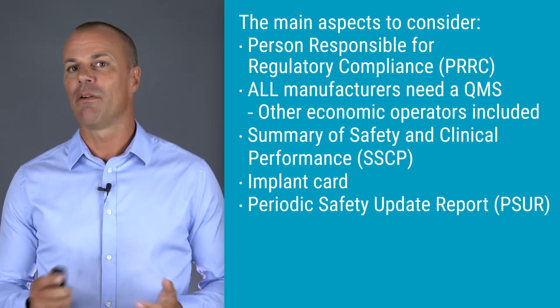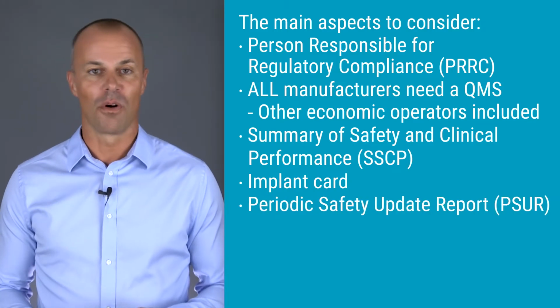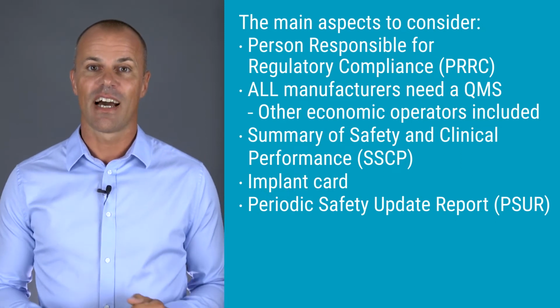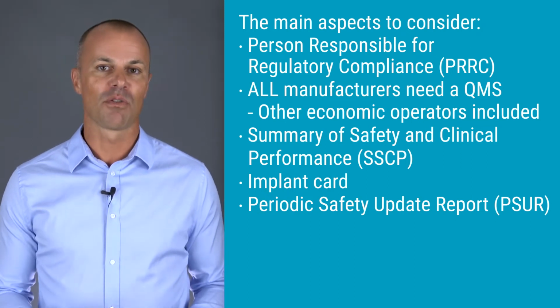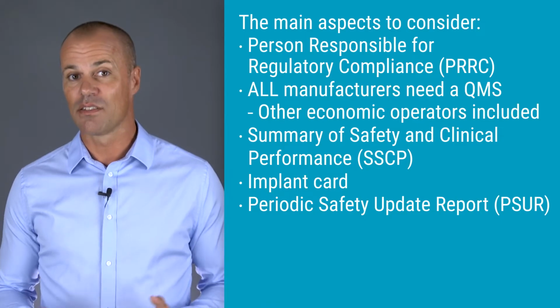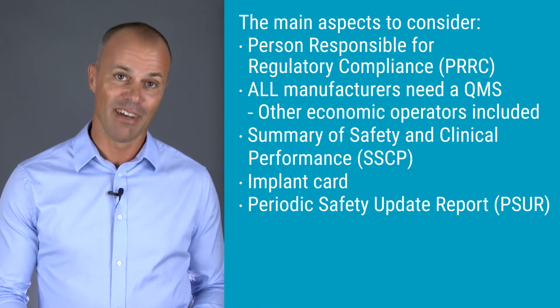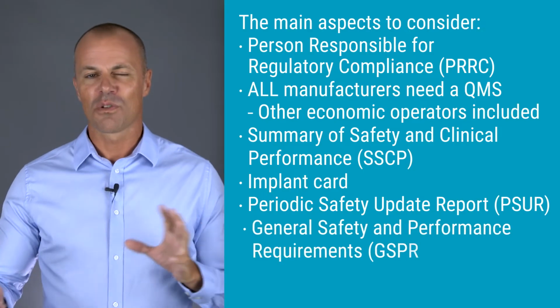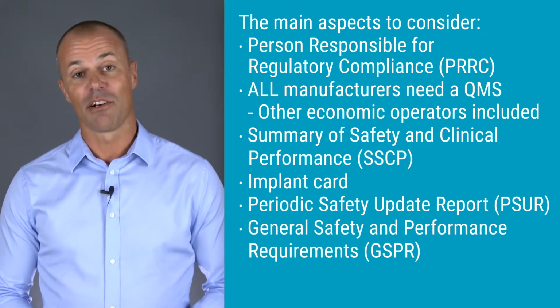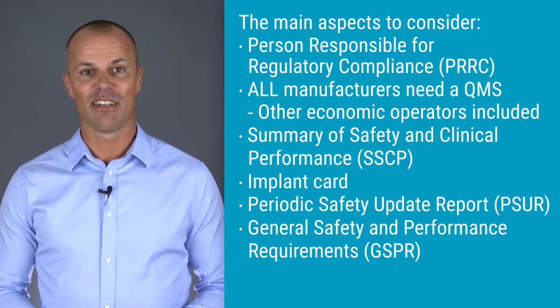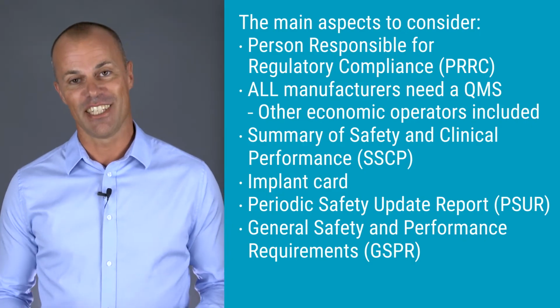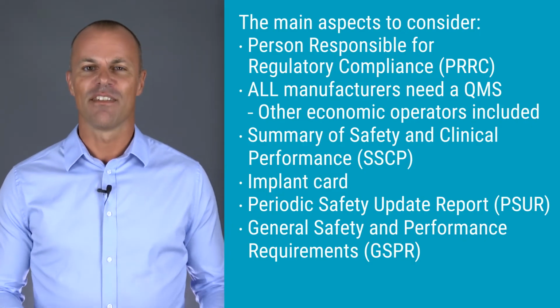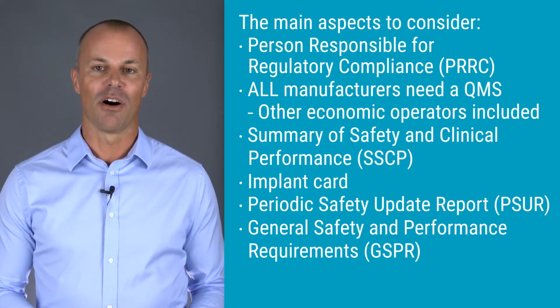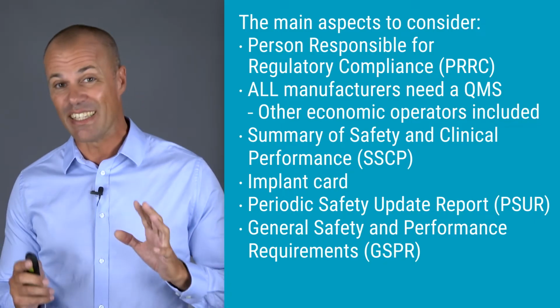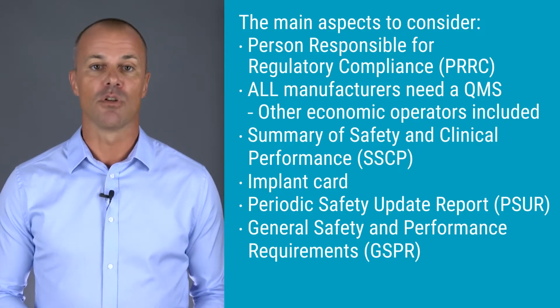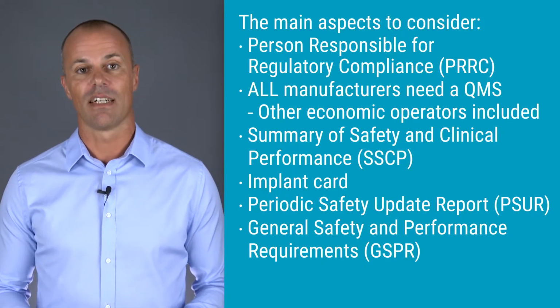Then we have the Periodic Safety Update Reports, or PSUR. This is kind of the results and output of the post-market surveillance plan, and it needs to be documented and also made available. What was earlier known as the essential requirements under MDD are now called General Safety and Performance Requirement, or just GSPR. This is a comprehensive 14-page part of the MDR, which covers general and specific device requirements applicable to all classes of medical devices.